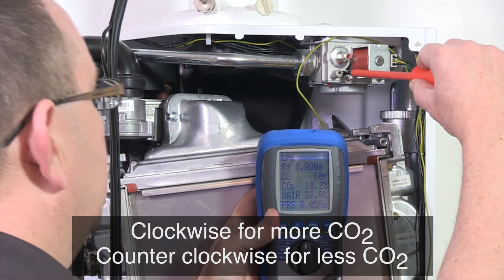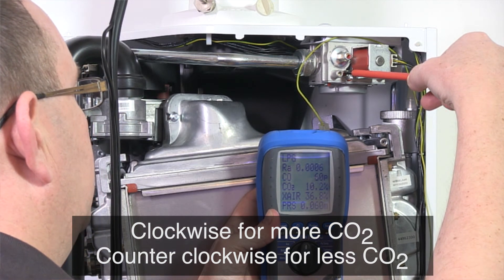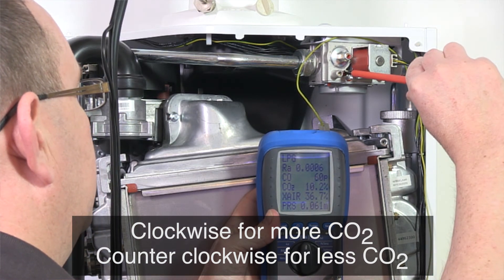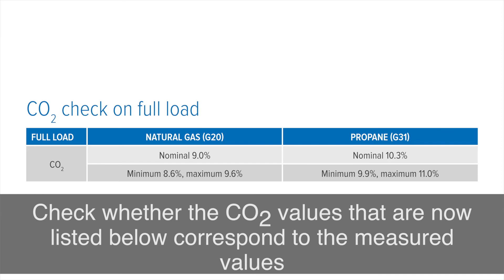Set the CO2 values using a 2mm allen key or a large flat bladed screwdriver on the throttle screw. Then turn clockwise for more CO2 or anti-clockwise for less. Then check whether the CO2 values now correspond with the measured value.